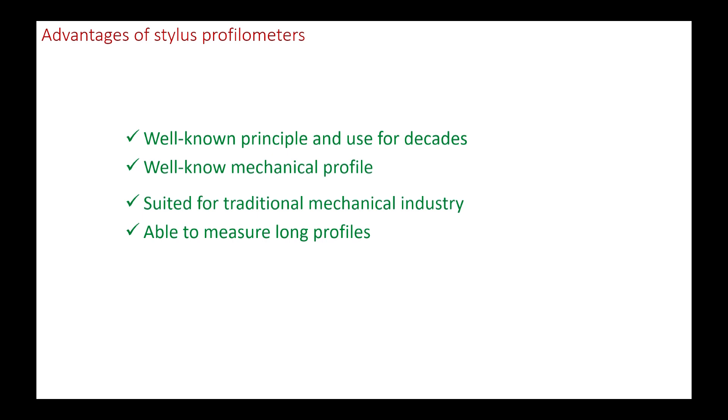The measuring length depends only on the traverse unit, which can be adapted to the needs. Some profilometers have lateral capabilities exceeding 500 mm. The technology is compatible with inexpensive devices that can be used in the workshop. All these advantages mean that the contact profilometer is still today the most widespread measuring instrument for the analysis of surface texture.